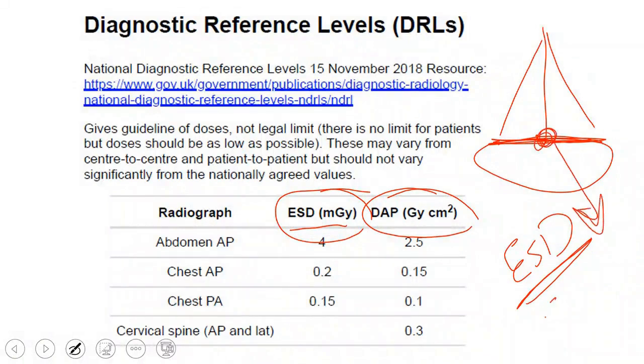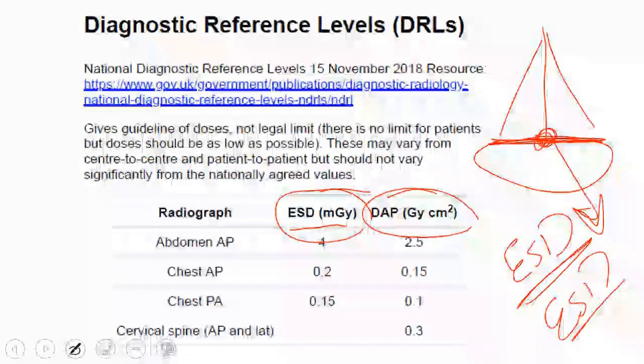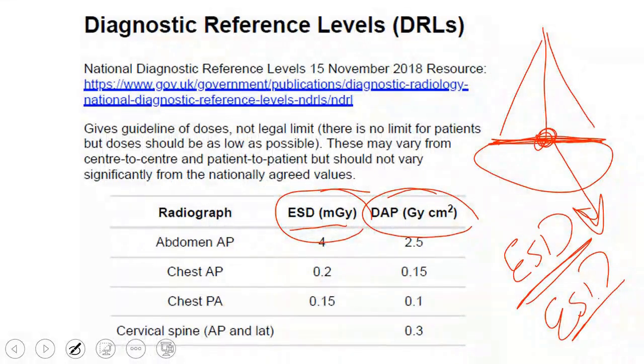This dose is automatic. When you enter the milliampere and input your parameters, it is automatically measured. This dose is per certain area, meaning that right now, for example, I have a specific field and view. This field and view have a certain area, and the dose multiplied by that area is called the dose area product. These two quantities represent the dose for the patient.